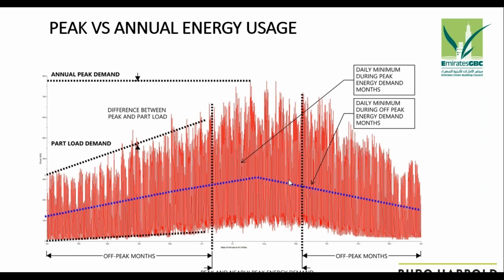However, if you inform your model properly, you realize that even during summers, at nighttime operation or on weekends, the building energy load is quite different from the peak - about a 50 to 60% drop-off in energy consumption. This is true even for off-peak months, where the peak part load is only about 50 to 60% of the peak load.